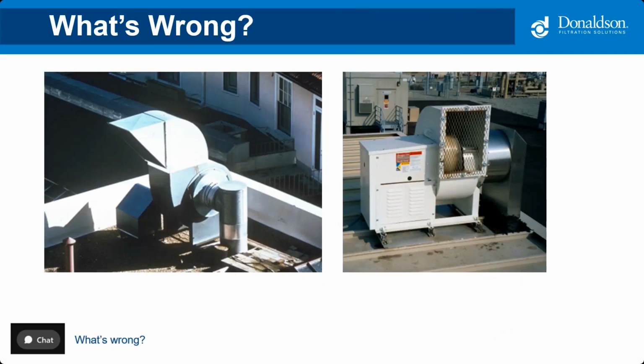Okay, these are just kind of fun. What do you see here? Bad inlets. Yeah, most people are pointing to that inlet. Looks like they listened to you earlier. No straight run of duct on the inlet.